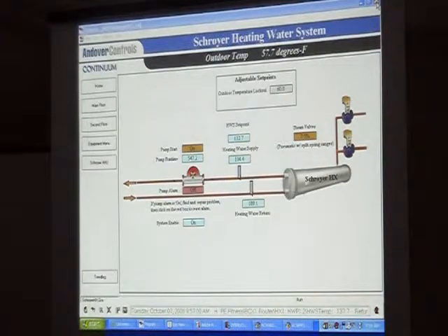Another thing that it means is, if you change something in the database with the controller offline and the controller comes back online, it'll tell you need to reload it. You get the same exclamation: object has been changed offline or edited offline, you need to reload the controller. So it's not necessarily an alert, because it's an exclamation mark. Right. It's a reminder. Yeah. It can be ignored for the most part. If you're having problems, you put your mouse over it and take a look and see what it says.